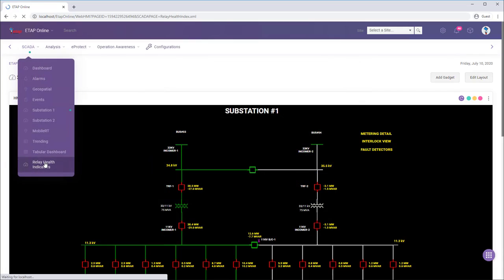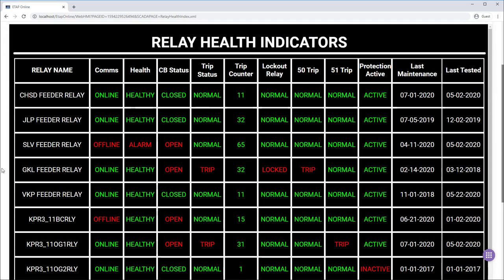In addition to the relay faceplates, we have the relay health indicators. Various parameters from the relay are monitored that are critical to the life cycle of the relays. This allows us to see how the relay is behaving, as well as historical maintenance information. This page is customizable, so you can determine which fields to monitor for a health index. In this case, we are looking at certain conditions in red. Under communications, we see that a few relays are offline, so we can't communicate with these relays right now. Specific breakers are tripped. You can also see a trip counter for maintenance purposes. We see the last maintenance and test date, which allows us to properly forecast for any future maintenance plans.